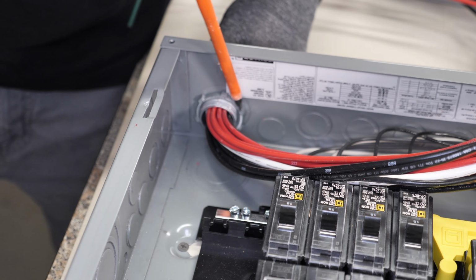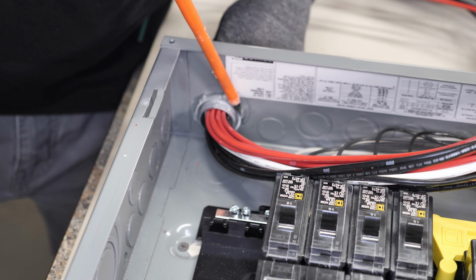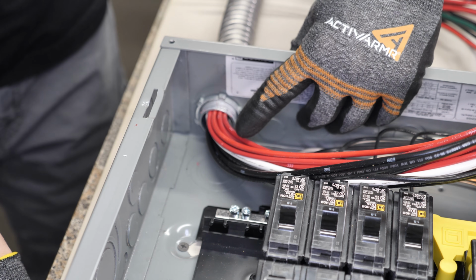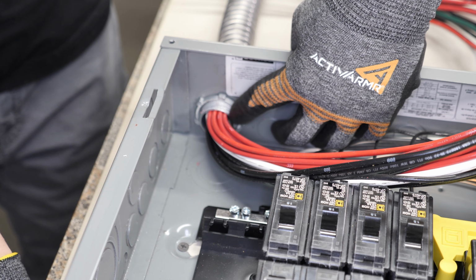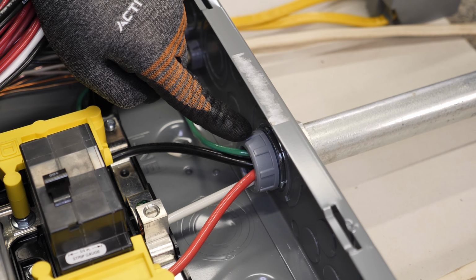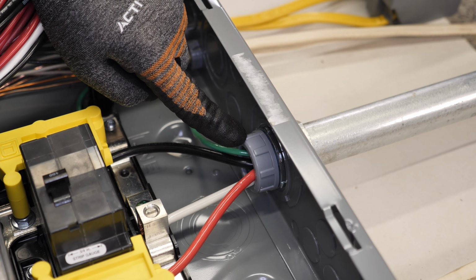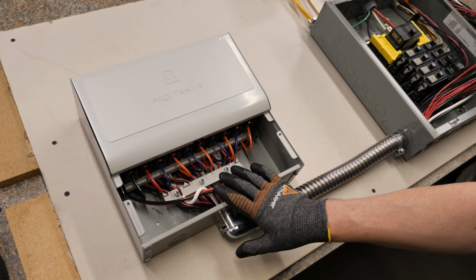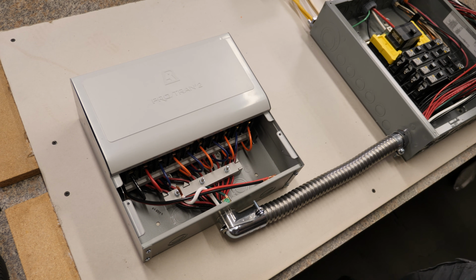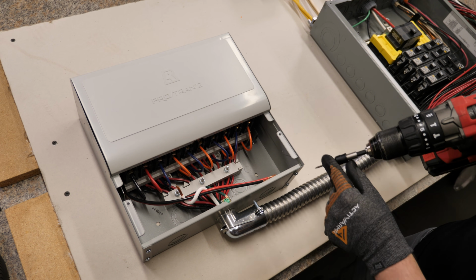What I always do here is just use a flathead screwdriver. Another thing you can install to help protect your wires is a plastic bushing, which I don't have at this current time. Next step is to finally mount the transfer switch to the wall, and since I'm on drywall, it's going to be super easy. If you're using tap cons, you should have drilled those holes earlier.